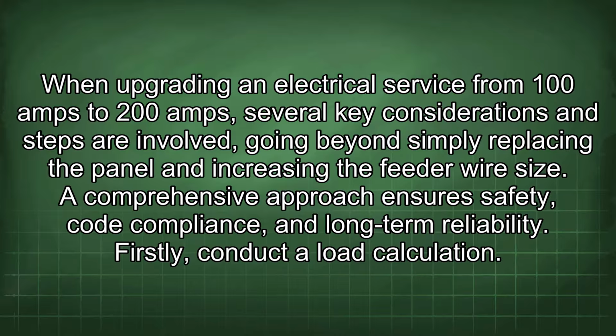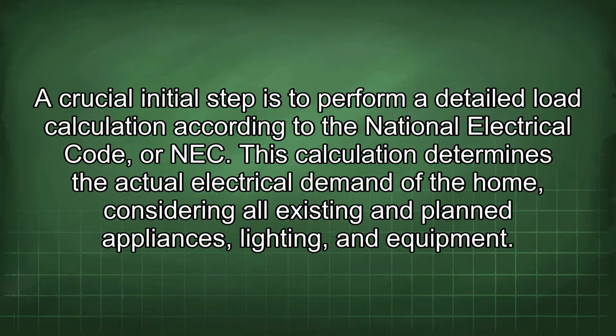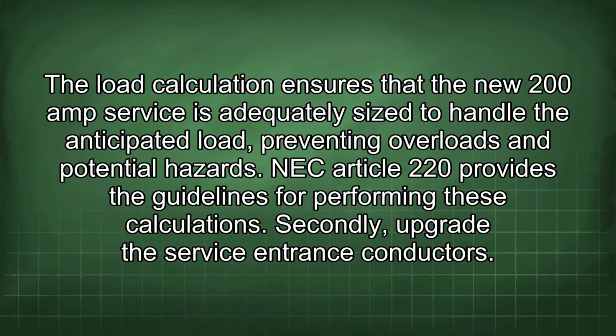Firstly, conduct a load calculation. A crucial initial step is to perform a detailed load calculation according to the National Electrical Code, or NEC. This calculation determines the actual electrical demand of the home, considering all existing and planned appliances, lighting, and equipment. The load calculation ensures that the new 200 amp service is adequately sized to handle the anticipated load, preventing overloads and potential hazards. NEC Article 220 provides the guidelines for performing these calculations.